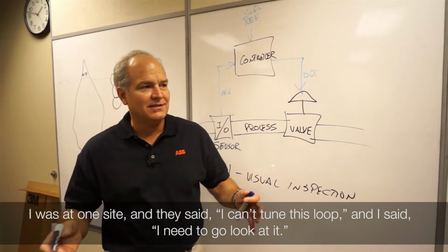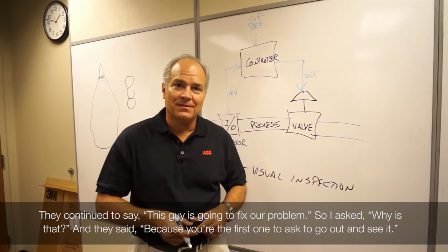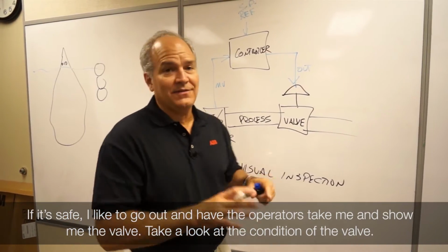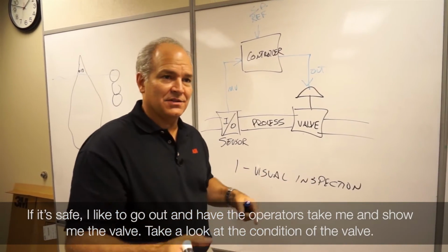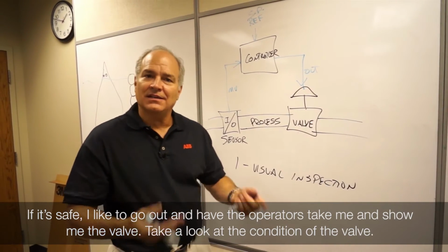I was at one site and they said, I can't tune this loop I said, well, I need to go look at it. And they're like, this guy's going to fix our problem. And they're like, why is that? I said, because you're the first one to ask to go out and see it. So if it's safe, go out and have the operators take you and show you the valve.